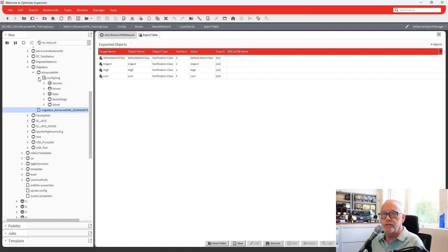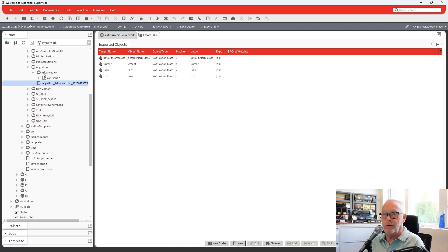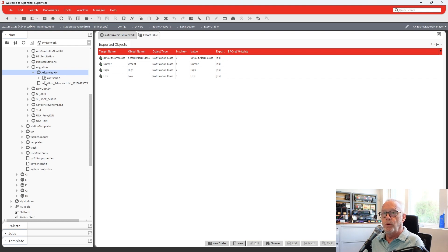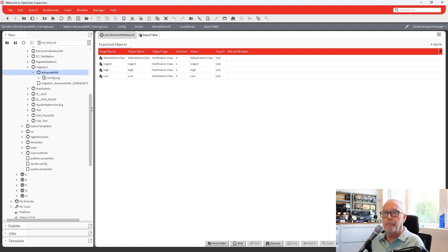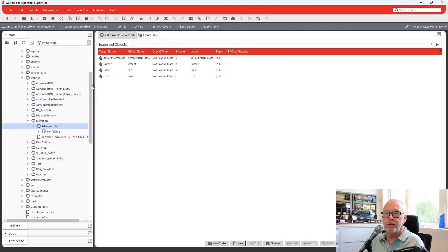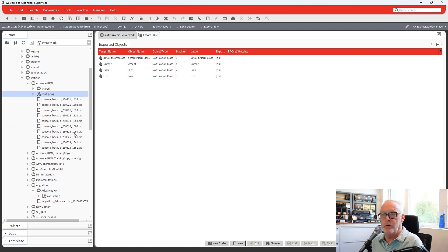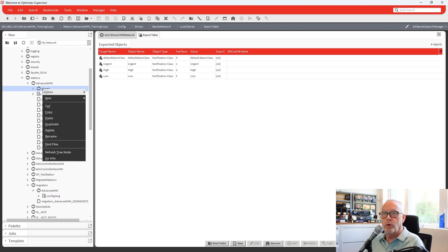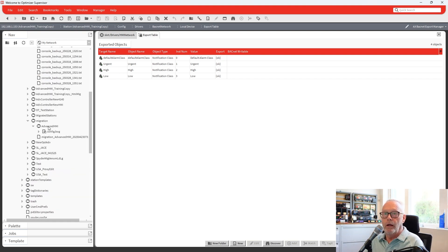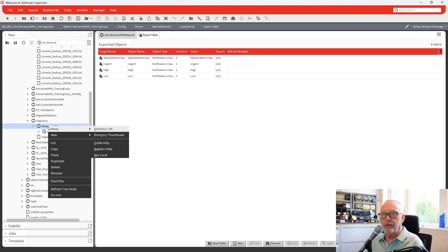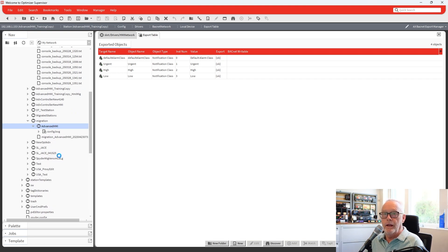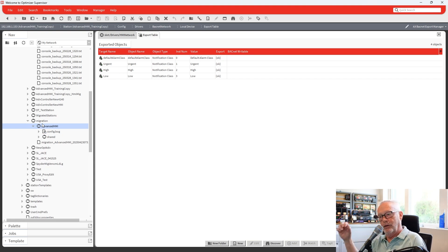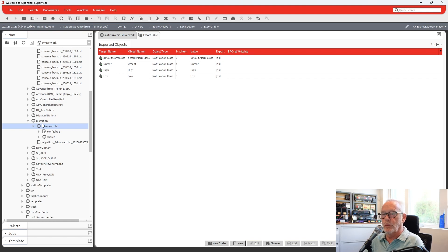One thing you will notice is missing within this station. I found that when you do the migration, the shared folder as part of the station does not come through with the config.bog. So if we look at the original station here, you'll see there was a shared folder as well as the config.bog. These console backups we don't really need to worry about. But this is important. You want to make sure you copy that shared folder and put it underneath your station in the migration folder. And now you have a complete station that you can then take and commission to your upgraded or commission with your upgrade that you would do on your advanced controller to bring it up to 4.14.0.